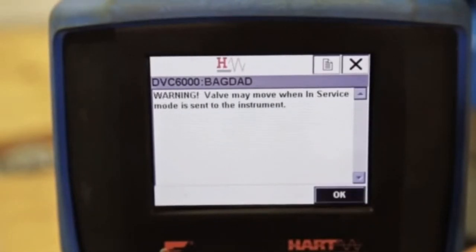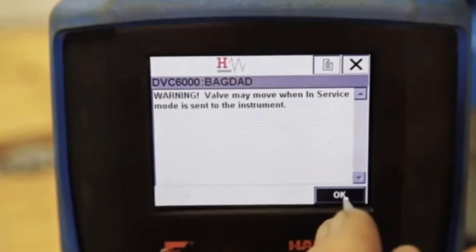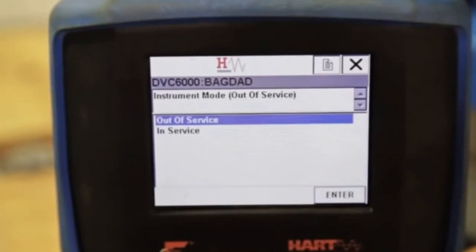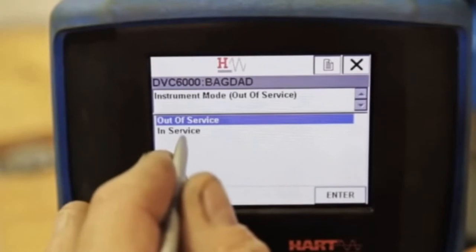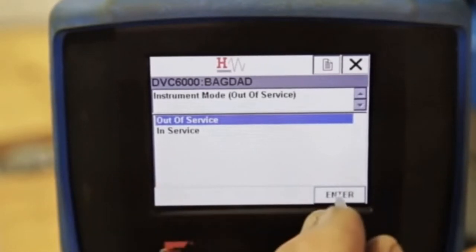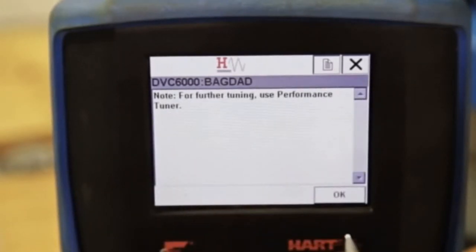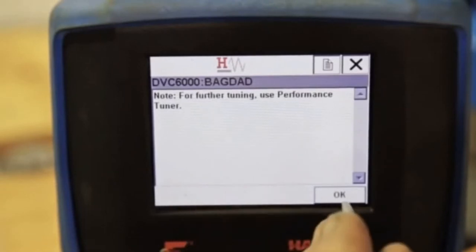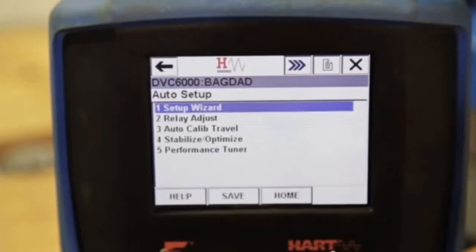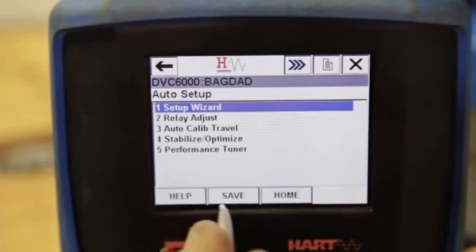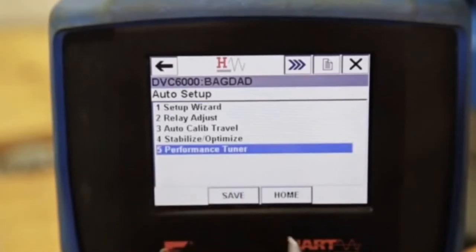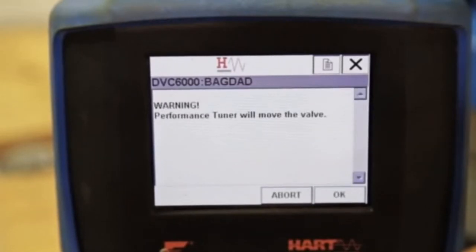Select OK for instrument mode. A warning that the valve may move when in service mode will appear. Since we want to run the performance tuner, select the instrument to be out of service. Now we'll run the performance tuner. Select 5. Warning, performance tuner will move the valve.